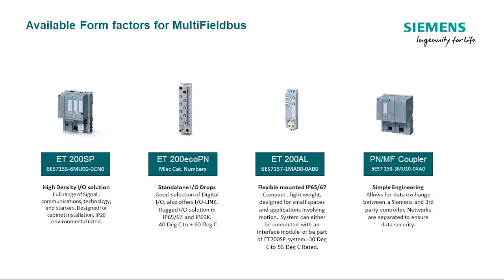Multifieldbus supports ET200SP, ET200EcoPN, and ET200AL. If you need to pass I/O information between PROFINET and another protocol PLC, this is easily done with the PNMF coupler. Configuration is done with a free software tool called the MFCT tool, which creates files recognized by Ethernet IP or Modbus TCP. For example, with Rockwell, you create an EDS file which is easily integrated into your existing project.